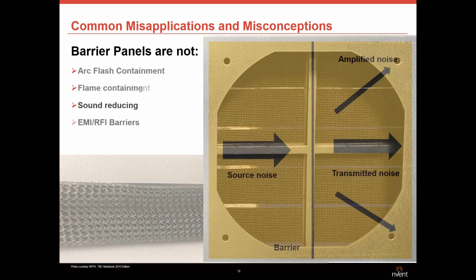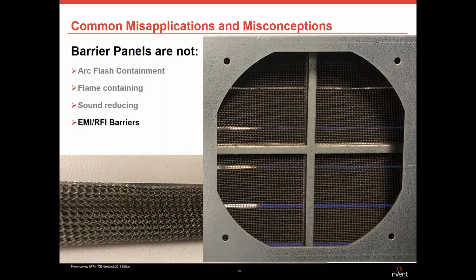The other thing that barrier panels are not is they are not EMI RFI barriers. To be an EMI RFI barrier, there would need to be a continuous bond around the holes, metal to metal, of surfaces bonding together. With any openings that may occur between the compartments, they need to be isolated by mesh. The picture on the right-hand side here is greatly exploded so that you can actually see that mesh underneath there. Even the gaskets need to be completely bonded. These are just a couple of the requirements. For complete requirements, please consult the proper standards.